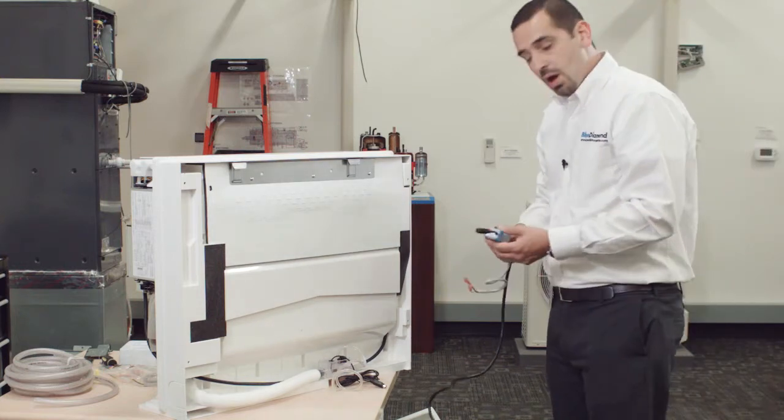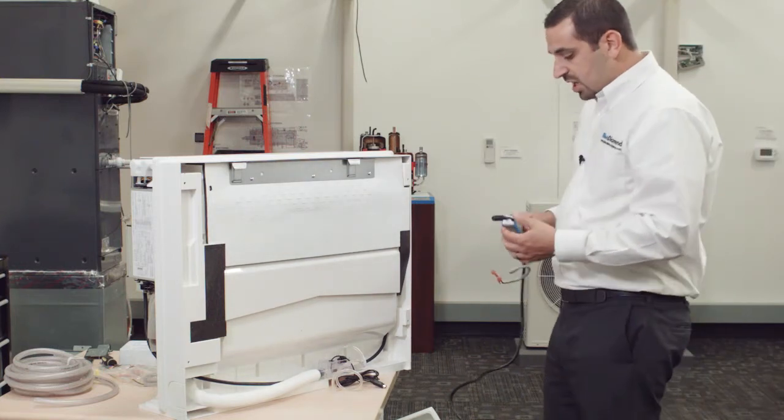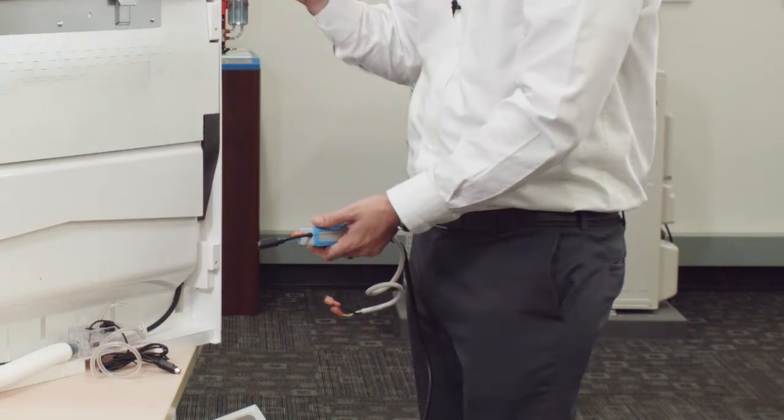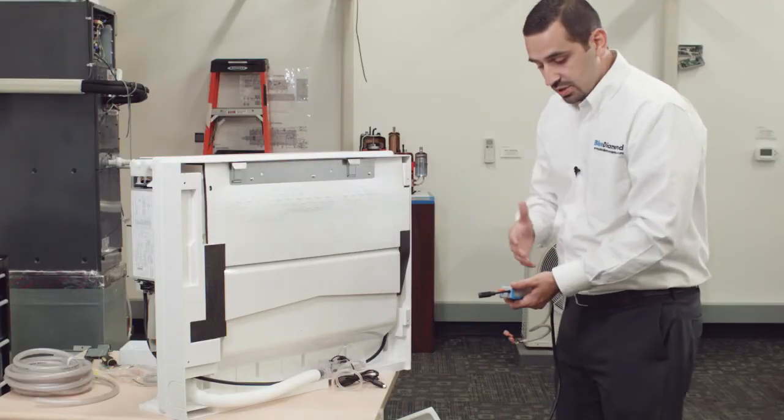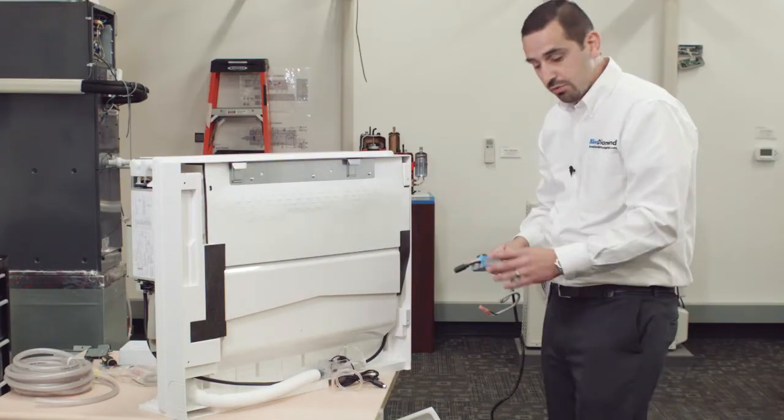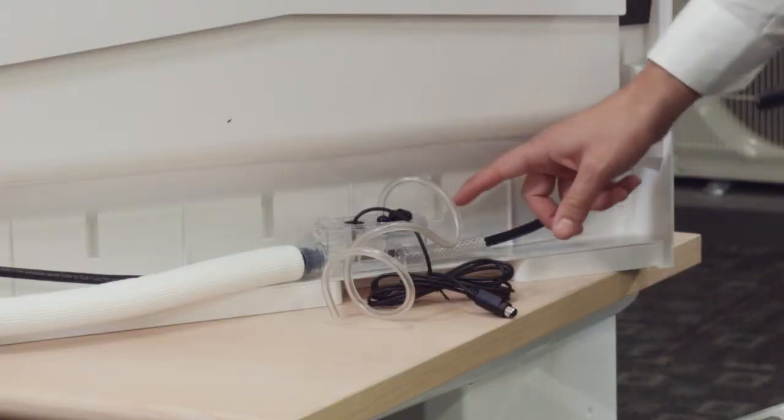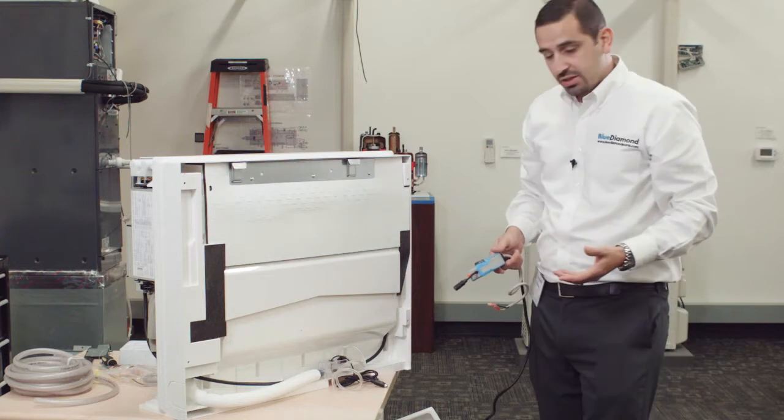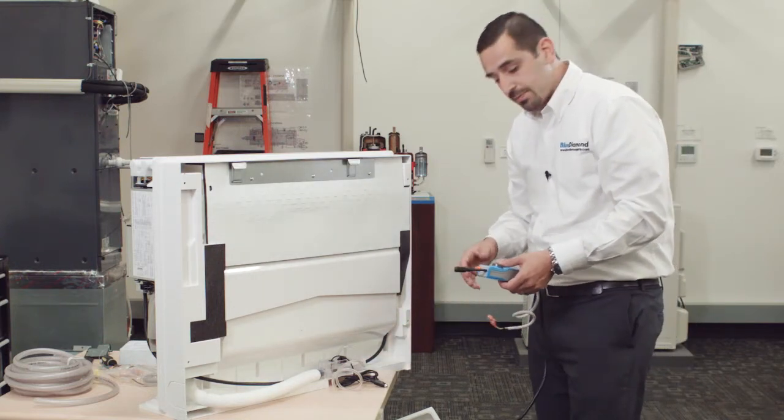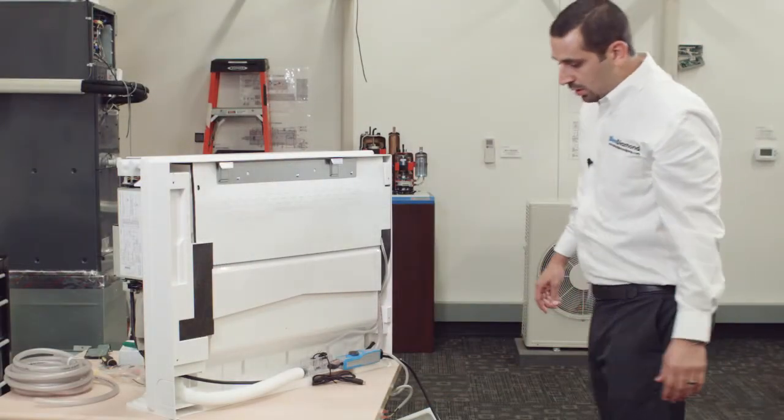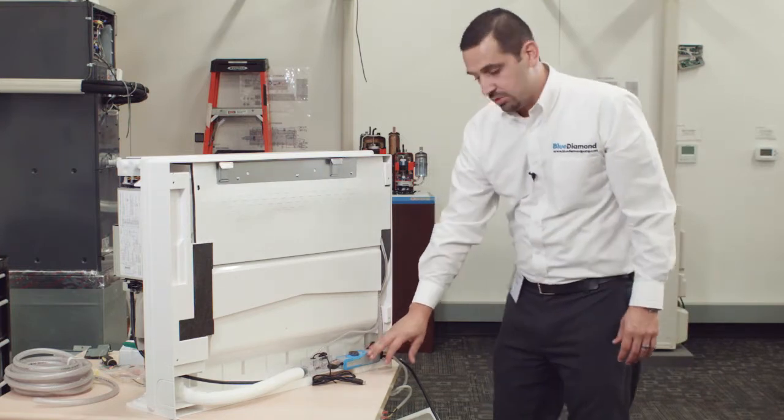Once you have the reservoir in place, then we want to put the pump back here as well. Keep in mind these pumps do create suction, so if for some reason you didn't want to mount it back here, you could mount it anywhere within six feet of the unit because it does create suction and it's a self-priming unit. We're going to adapt it to the reservoir with quarter inch ID tubing.